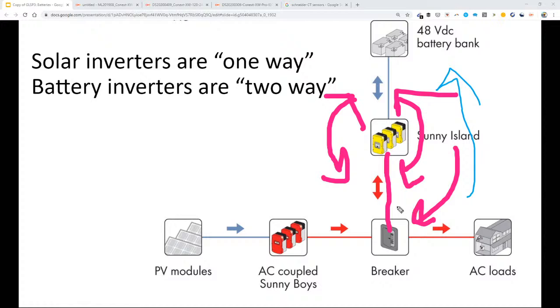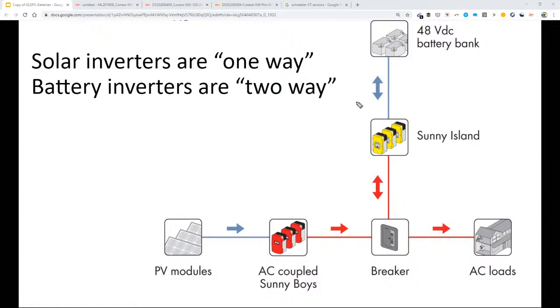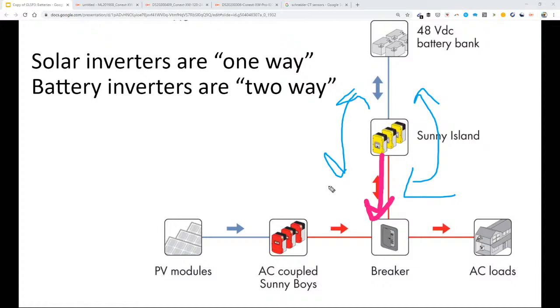So you can buy battery inverters with batteries that are just one-way, protecting critical loads, for example. But most battery inverters—like the Tesla Powerwall—are two-way: they can charge from the grid and discharge to the grid. One of the pitfalls of selecting a battery inverter, as we'll discuss, is that the charging-to-grid feature isn't always as functional as your imagination will allow.